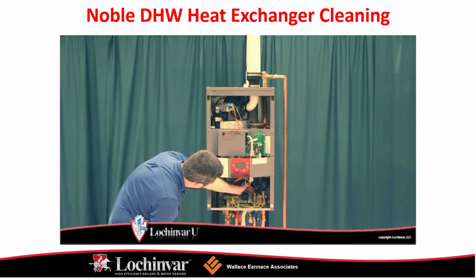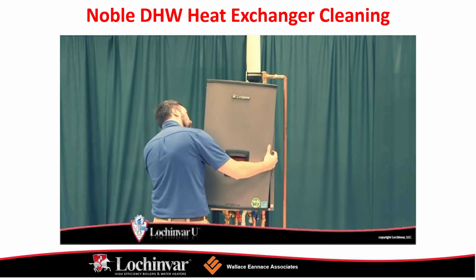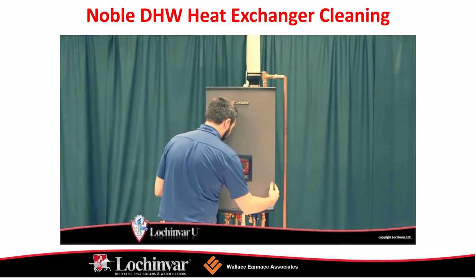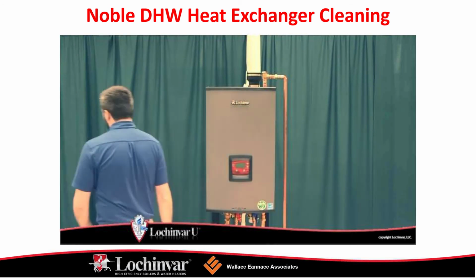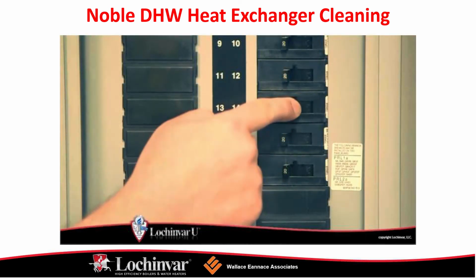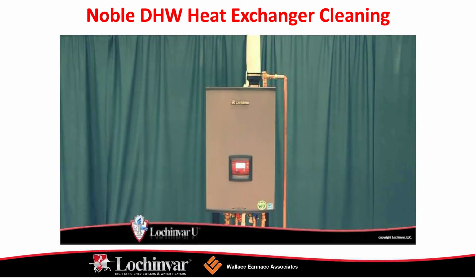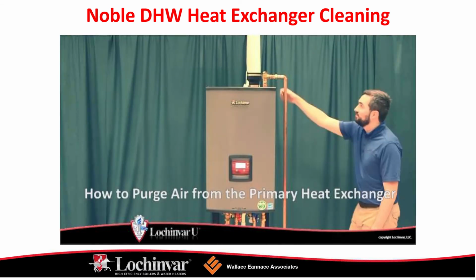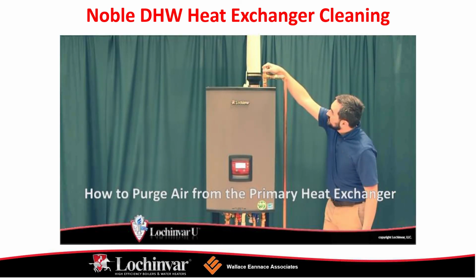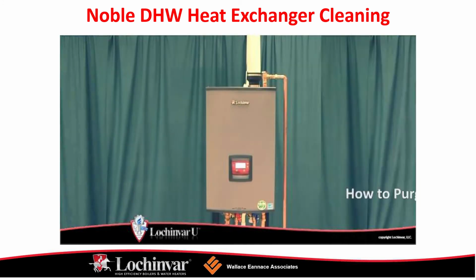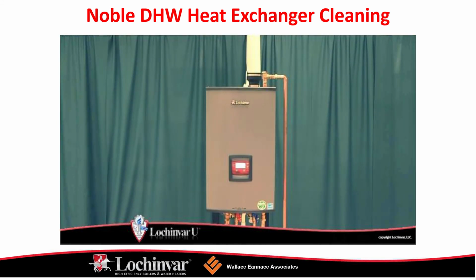The Noble heat exchanger cleaning. Replacing the brazed plate heat exchanger. Turn off the main power to the unit. If the unit has been in operation, allow the unit to cool to room temperature before proceeding. Close the valves on the water piping and drain both the primary and brazed plate heat exchangers. Remove the front access panel from the unit.